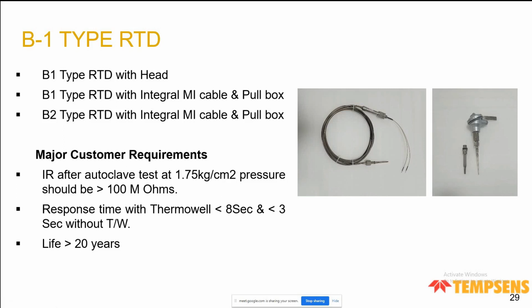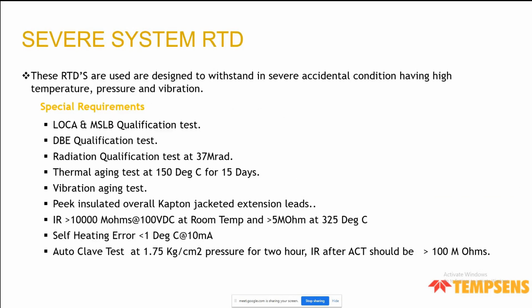And again the same requirement of more than 10,000 megaohm insulation resistance at room temperature. All these RTDs, the last one and this one, have to be tested in an autoclave at 1.75 kg pressure for more than an hour, and the insulation resistance should remain good. So those are the basic requirements for this RTD.